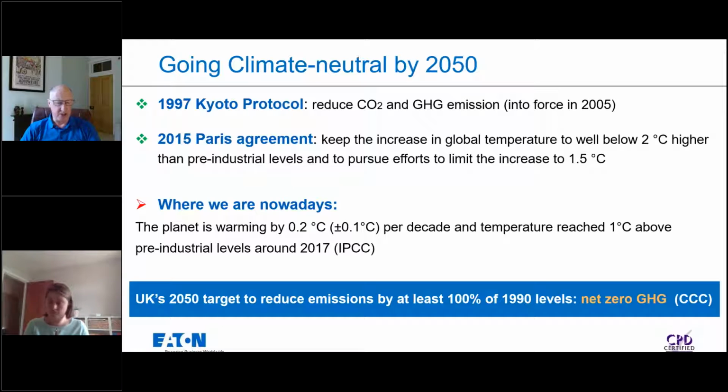Methane, for example, has a much higher global warming impact than carbon dioxide. Depending on the source you look at, that's typically between 25 and 35 times. So it'd have a global warming potential maybe of 30. One of the greenhouse gases named in the Kyoto Protocol was something called sulfur hexafluoride, which some of you may have heard of. The reason I mentioned that one is because it is the most aggressive greenhouse gas known to man, and it has a GWP of 23,500.